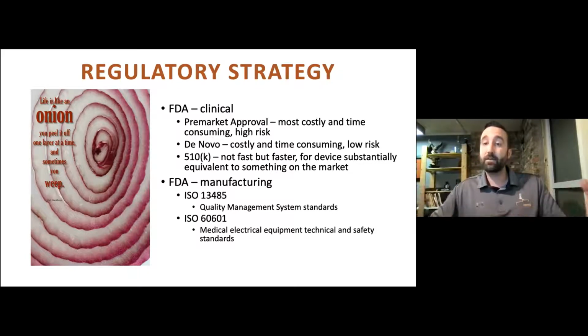So if you can find a pathway that's much quicker via de novo, or even better 510K, meaning there's a substantially equivalent device on the market already, that's really what you want to go after. But regulatory strategy doesn't end just at the FDA, or it doesn't just end at the clinical part. You also have to look at things like your ISO 13485 and your 60601. That's going to be your manufacturing standards to make sure that you're meeting all current good manufacturing practices.